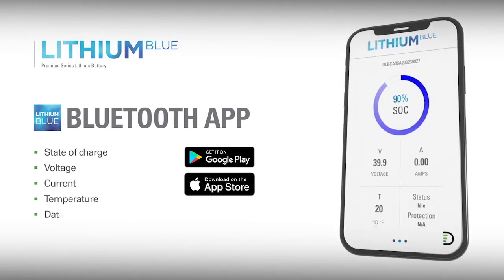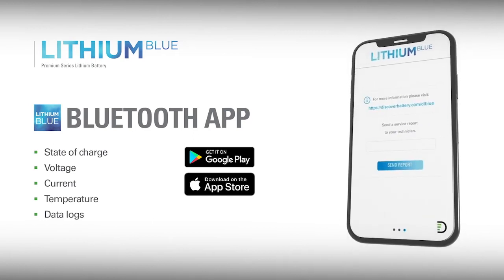So you get that nice firm hold up over a period of time. That also brings some interesting challenges and advantages to lithium. Because it's like that, it would be hard to monitor state of charge using an external device. But it offers a very predictable state of charge because of the digital capability of the BMS in that battery. You can read that information, and get very precise state of charge information off of a lithium ion battery using a digital BMS. We have a Bluetooth app that provides that to users' phone or iPad. So it's very easy for them to see the state of charge of each battery that they have, and get that long hold up and strong power right to the end of the usable capacity.